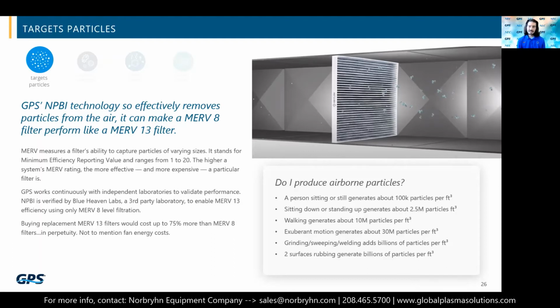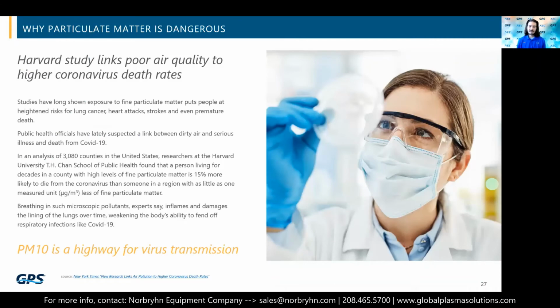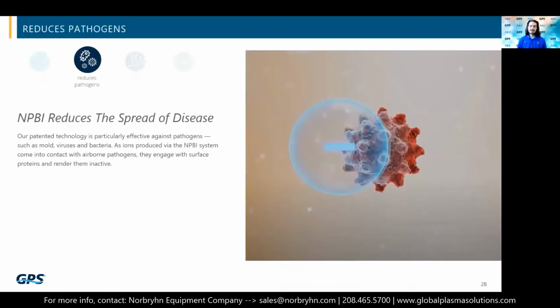In this lab study, they took a MERV 13 filter and showed how clean it gets a room, basically showing what size particles and how many there are after you run the MERV 13 filter for a while. And then in the second parallel example, they started the room with the same amount of particles and then ran a MERV 8 filter with ionization. Over a period of time, you see the room come down to the same size and quantity of particles as the MERV 13 achieved. And so what they see is about a 4 to 5 filter rating increase when applying ionization. And this works for any existing filter system. So if you have a MERV 8, you can increase to a MERV 13. I'm getting ahead of myself here.